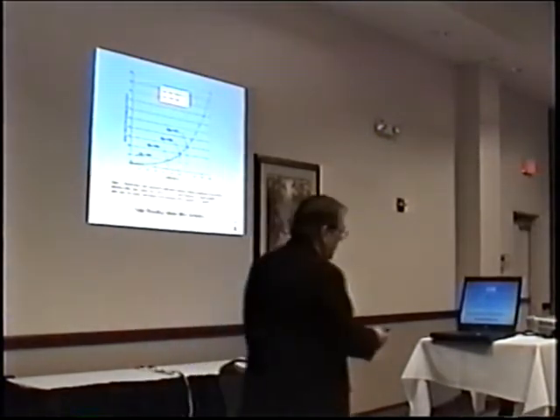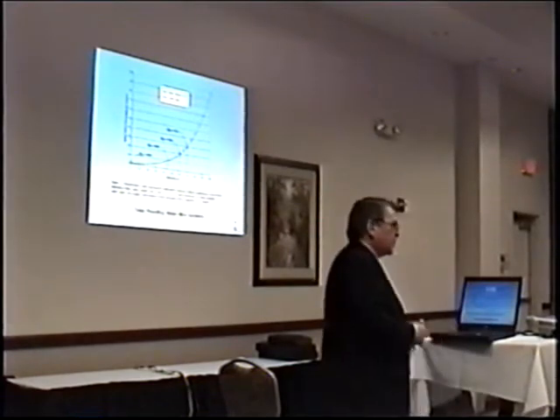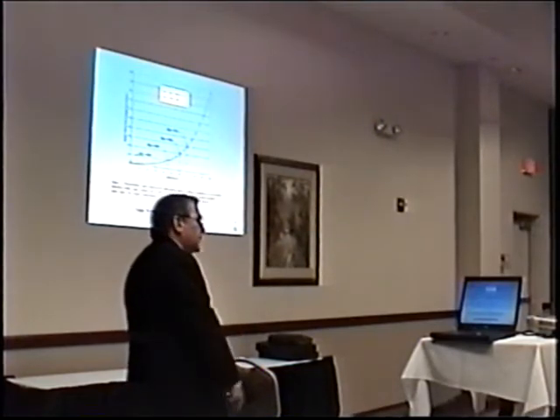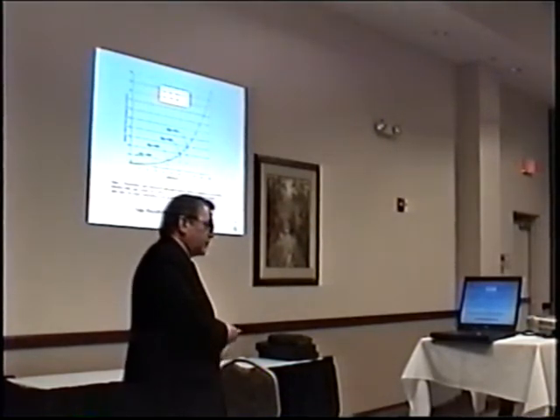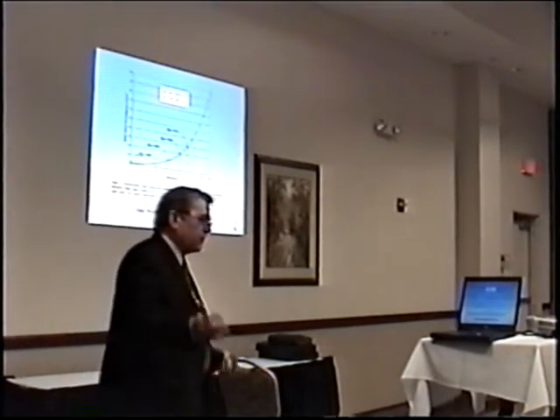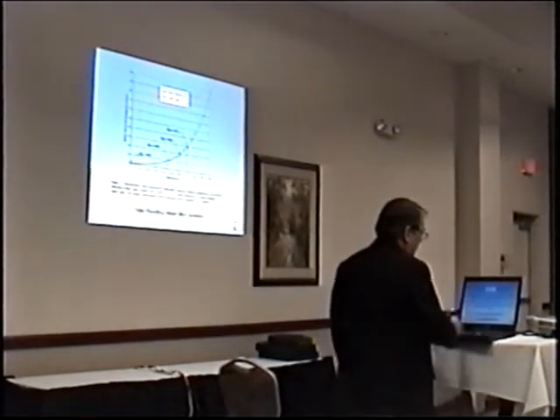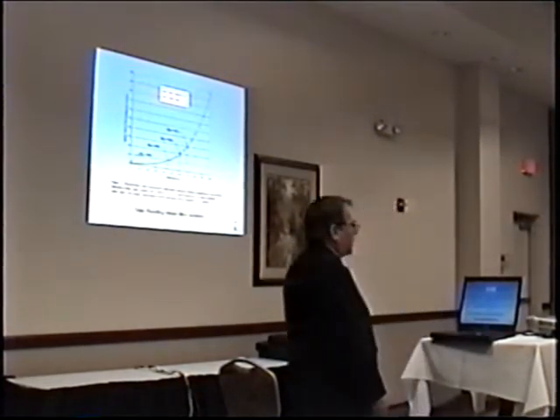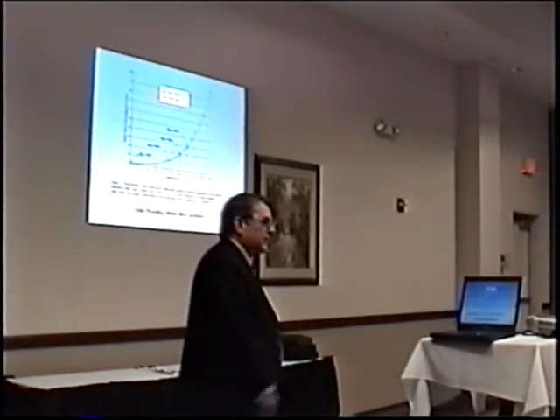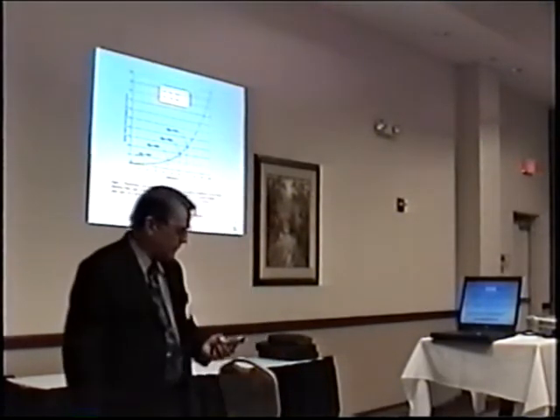Basically, the systems that I was brought in to evaluate, I had to say for a hydrocarbon fire in a space where the flame is exposing 1,200 PSI methane gas piping and flanges and pump lamps, I don't want flames raging in there for 3 minutes unsuppressed. And I had to eliminate the 3-minute downside. But a pre-engineered system installed within its volume listing is going to be pretty straightforward and pretty safe to install.